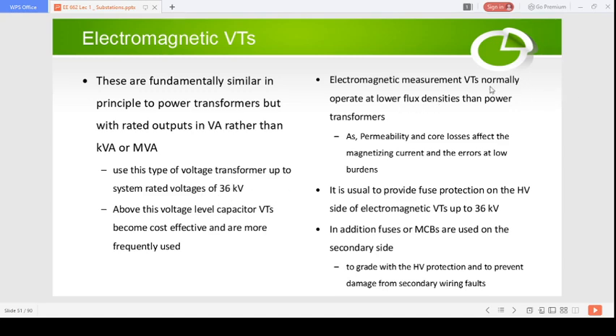These electromagnetic voltage transformers normally operate at lower flux densities than power transformers. Power transformers are operated at high power as well as high flux density, but electromagnetic measurement transformers operate at low flux density. So it is usual to provide fuse protection on the HV side of the electromagnetic VTs up to 36 kV. We talked about the protection of these CTs and PTs when we discussed disconnectors, circuit breakers, and fuses. In addition, fuses or MCBs are used on the secondary side, because the secondary side currents and voltages are lower compared to the primary side.